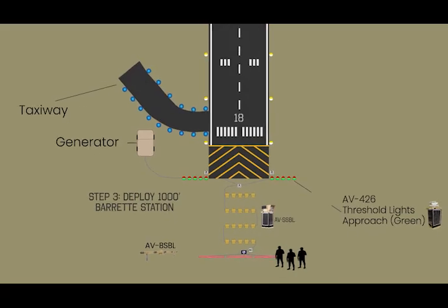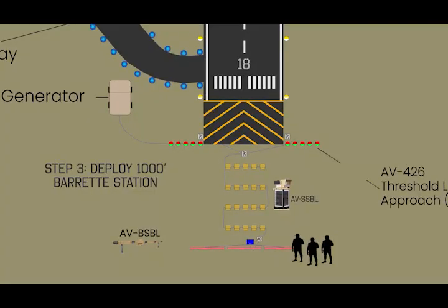Critical step. Connect the 3 barrettes to the large battery box using only the 40-foot DC cables. Do not connect AC lines directly to the barrettes. Then connect your main AC power line to the battery box using the breakout cable.